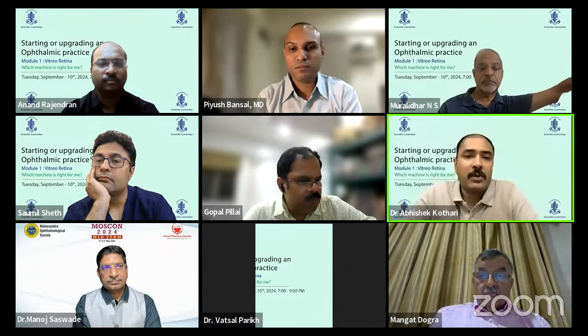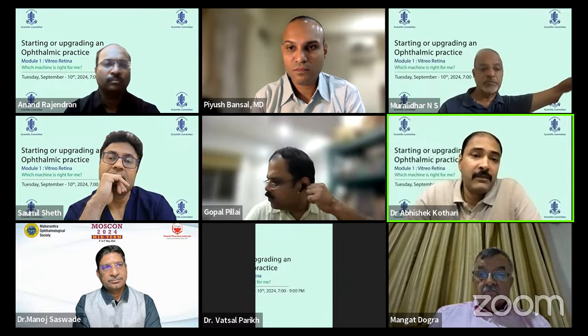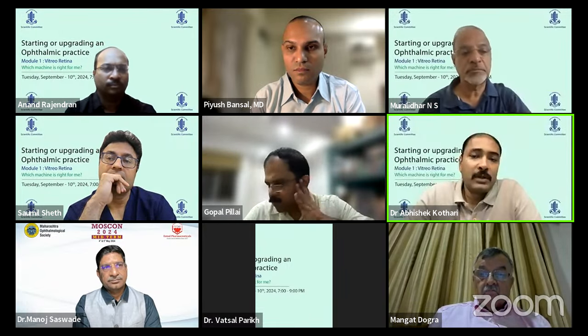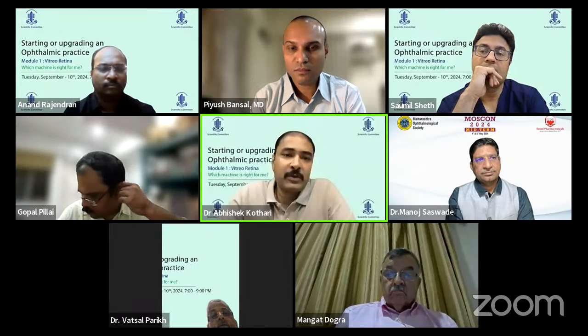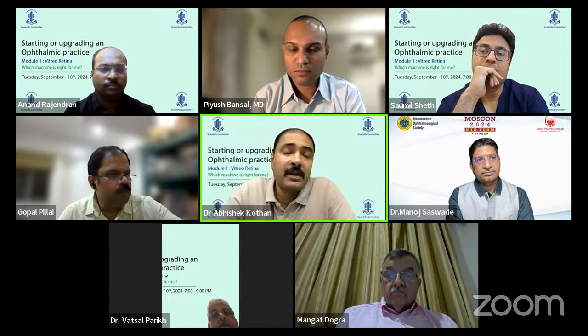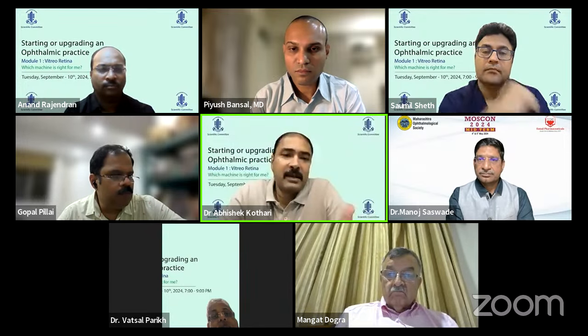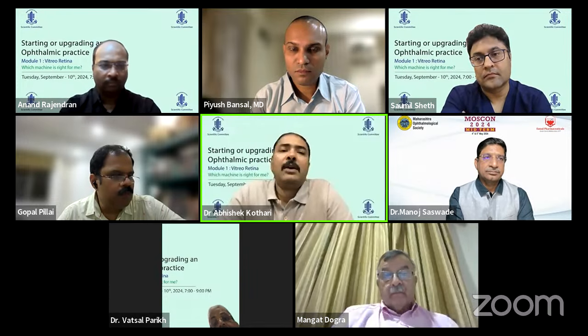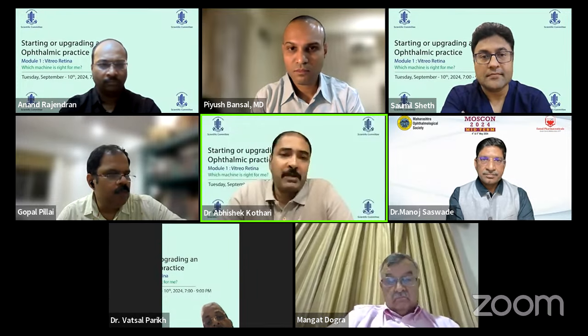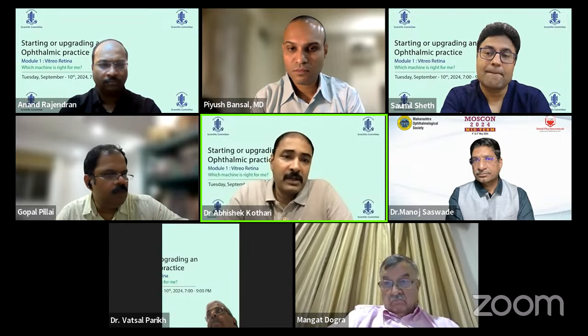Yes, so Dr. Manoj rightly pointed out, a microscope is something that requires very infrequent service. So a second-hand microscope is absolutely fine, provided the optics are great. Always look at the prices compared to the features of the microscope. I mean, Zeiss is there, Leica is there, Moller-Wedel is there. All three have excellent options, and all of them are BIOM compatible, VR compatible. So you really don't have too much of a problem selecting between them.